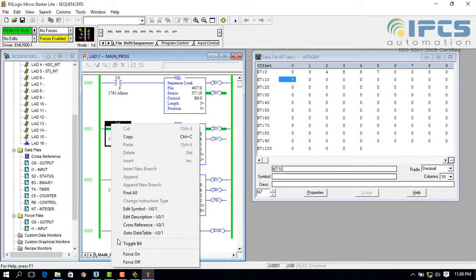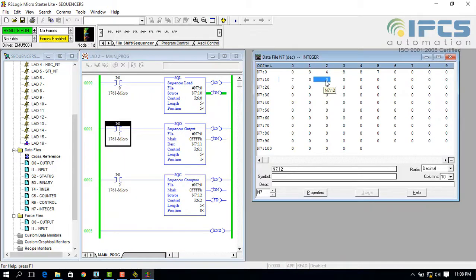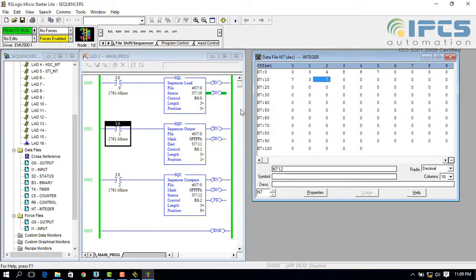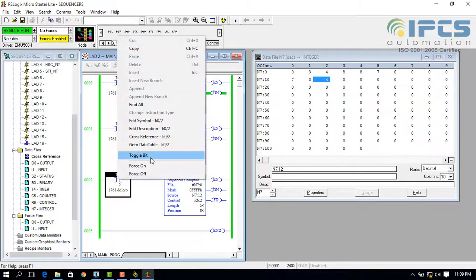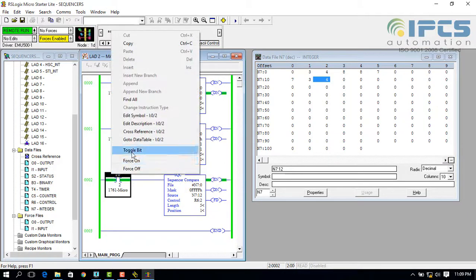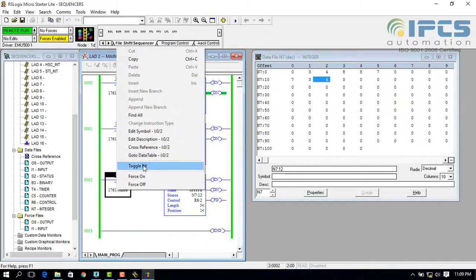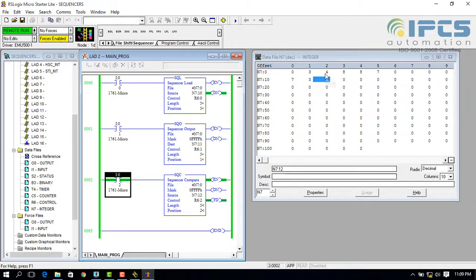Now, let's see how sequential compare works. The value to be compared is placed in source, which is N7 12 in this program. With each low to high pulse, the position increments and the value is compared with source value. Here the source value is found at second position and found bit is made to its high value.